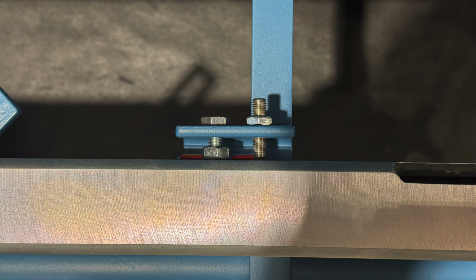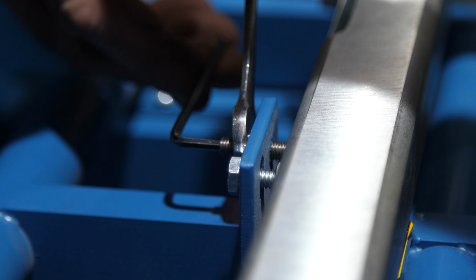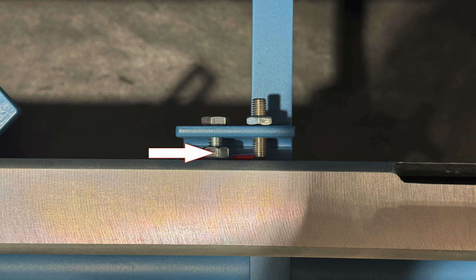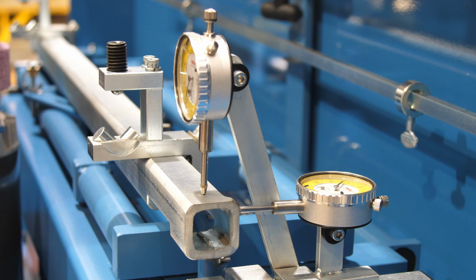You'll want to hold the set screw with an Allen wrench as you do this. You do not want this set screw distorting the V-support bar. Again, it's just reinforcement, not an adjuster. You can then end by tightening the jam nut on the adjusting bolt, watching the dual dial indicators as you go through this entire final tightening sequence. Finally, always end with the dual dial indicator as confirmation that you're within spec of 2/1000ths of an inch on both faces.